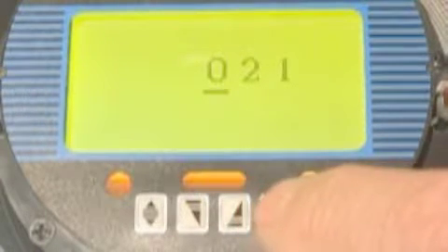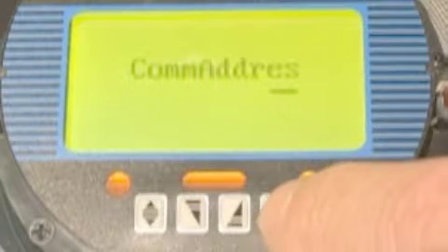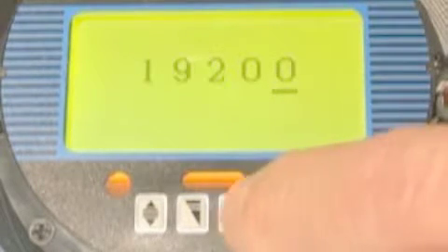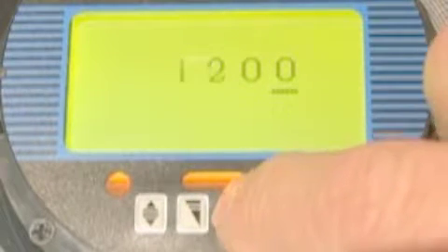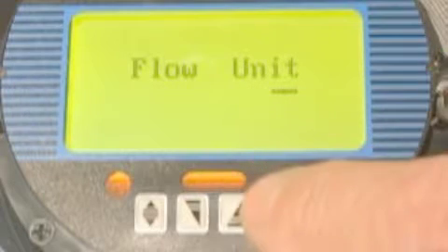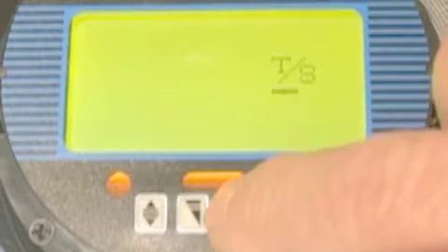There are five levels of passwords. So enter and we can look at the baud rate, 19.2, 38.4. We can see what's available. In here, we look at the baud rate, sensor size, flow unit. Here are the flow units that are available.